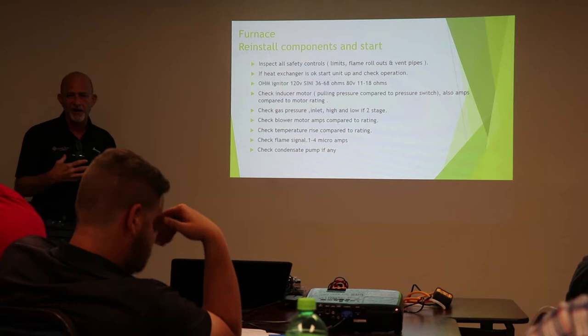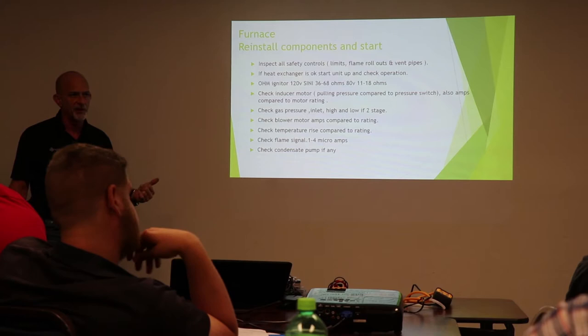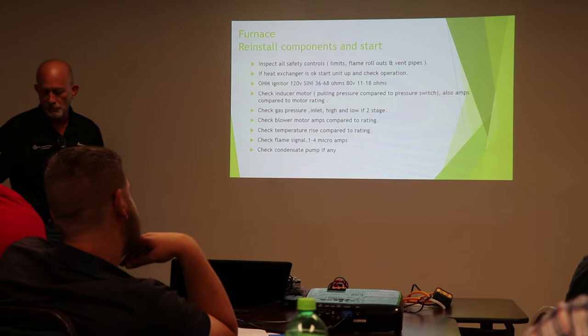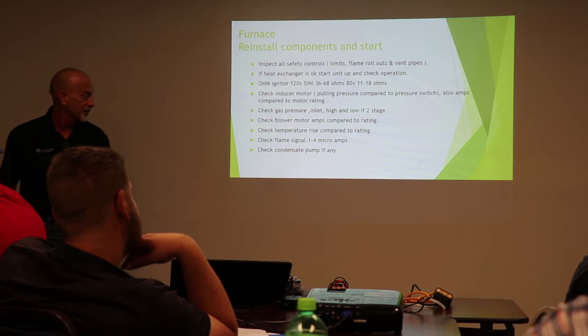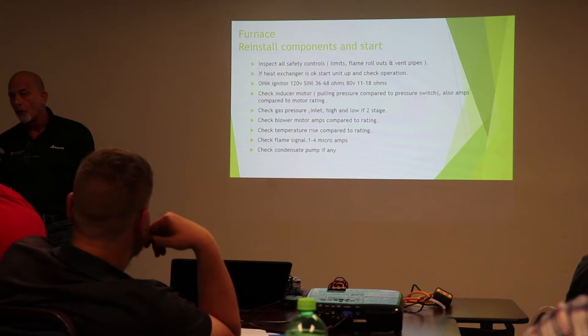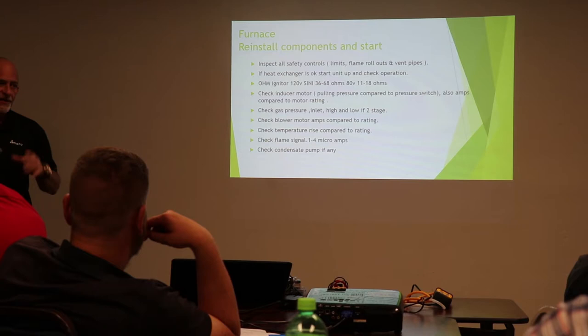Our biggest offender is 80% equipment. Because usually when you go do a clean check on an 80% furnace, where's the litter box? Right next to the furnace. Mm-hmm. Always. Homeowners love putting it there. It's in their laundry room. It's the worst thing for a furnace. Try to encourage them to move it. But flame rod, you want to be between 1 and 4. The higher, the better. Once you get below 1, it starts becoming weak.